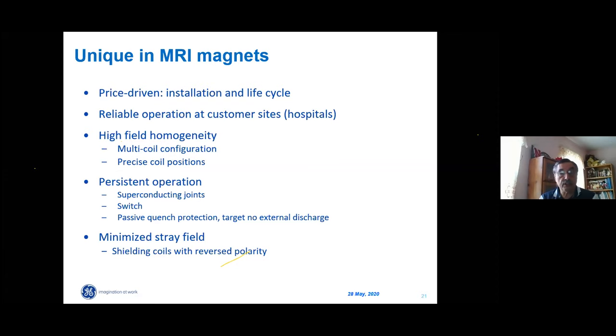What we need is very high field homogeneity, multi-coil configuration, precise coil positioning. We also need persistent operation of the system because we need very high field stability. And we need a minimized stray magnetic field. One line that I missed here, we'll discuss it later: emergency rundown. What happens if a patient, for whatever reason, experiences pain or requires immediate attention? We need to ramp the magnet down immediately. The only way to ramp the magnet down immediately is to quench the magnet. Immediately means in less than 30 seconds. So we need to have the ability to ramp the magnet down immediately.